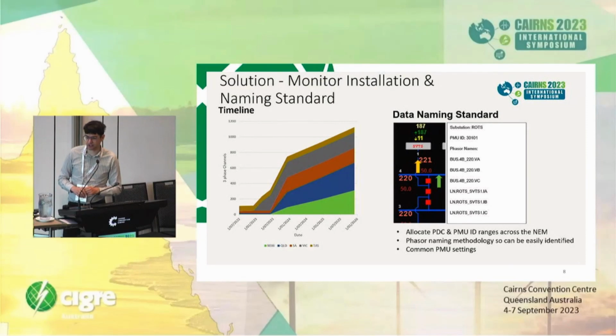To facilitate this, we've also come up with a naming standard and guidelines and standards around PMUs and what the minimum requirements are. Obviously, we can't say we want a specific PMU to be installed at any given place, so we've leaned heavily into the standards, so the C37.118 2014 standard for accuracy and reliability, as well as things like coming up with naming standards so that we can easily identify and expedite connection and integration of the PMUs into our system.